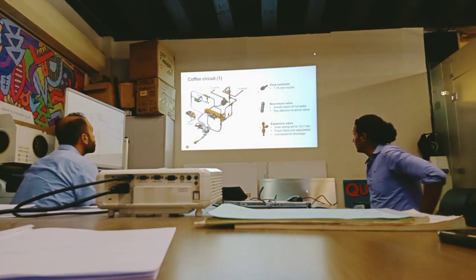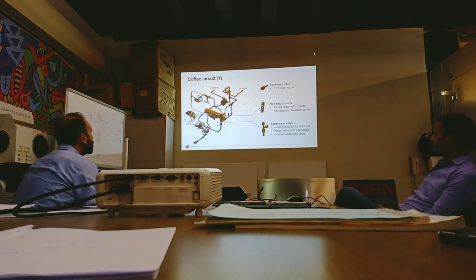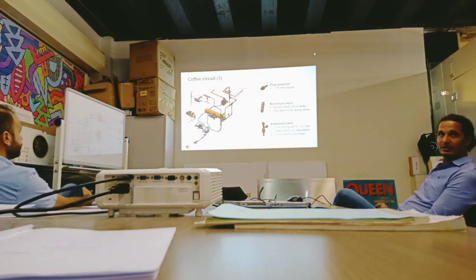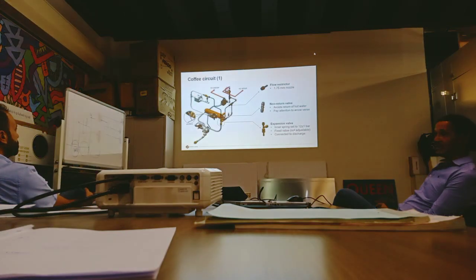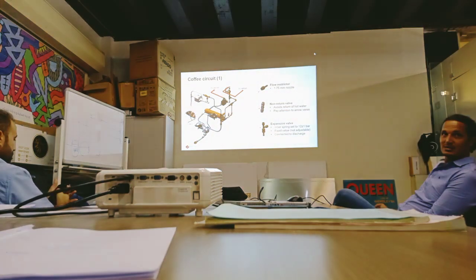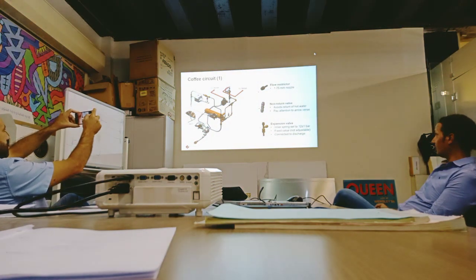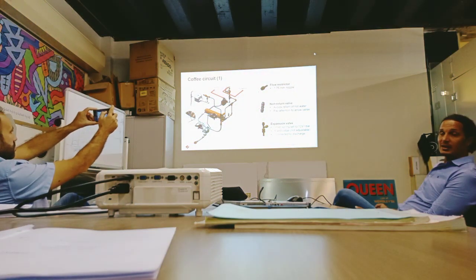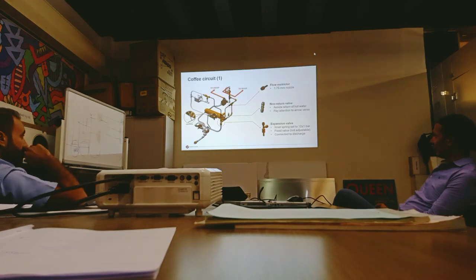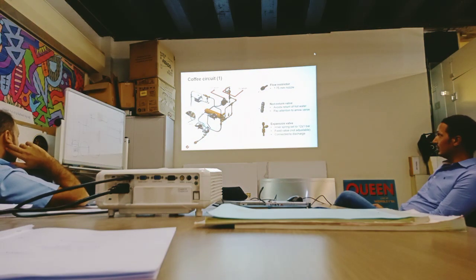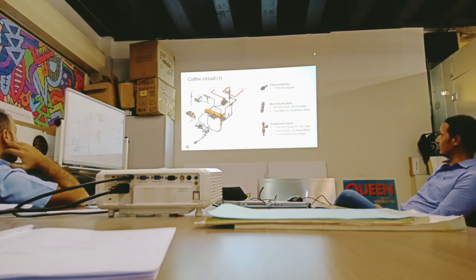No other question here? So this is what we were explaining on the circuit. From the line to the electronic valve, the pressure reducer, coming out to the heat exchanger, we have this expansion valve. This expansion valve is set at 12 plus or minus 1 bar. It's a fixed value, as I mentioned. You cannot adjust it. Do not try to adjust it or clean it. It's very difficult. If it's defective, just remove it and put another one. It's connected to the discharge, meaning if there is any high pressure in the line, this expansion valve opens to release the extra pressure and it goes to the drainage.